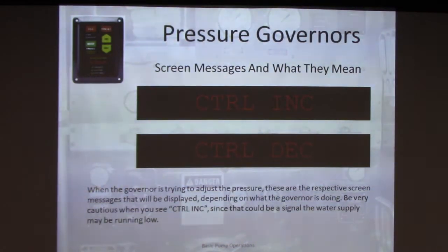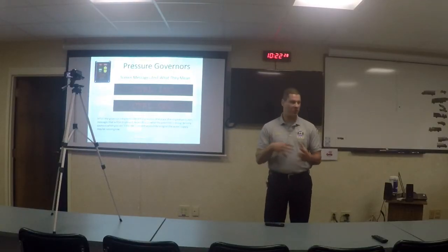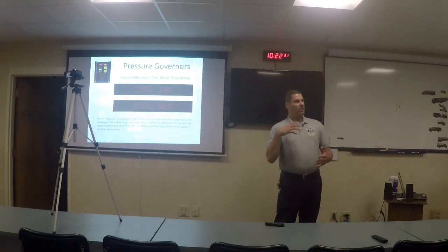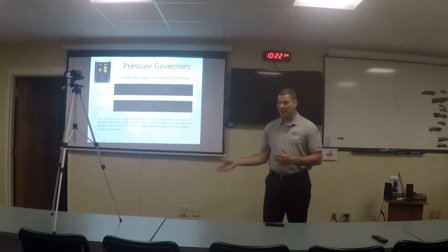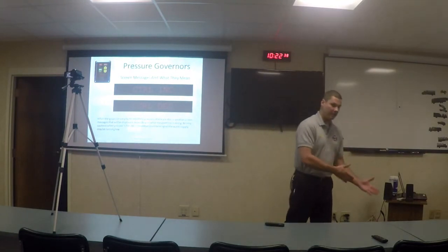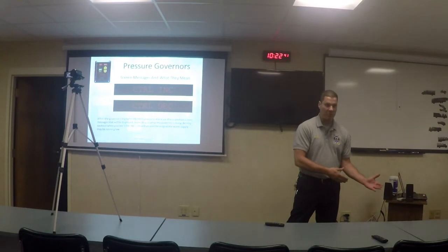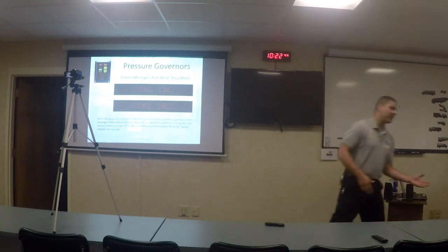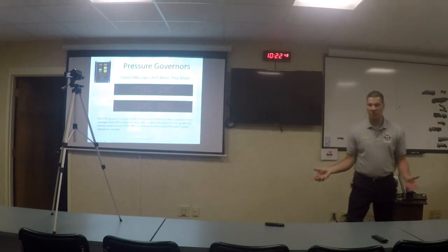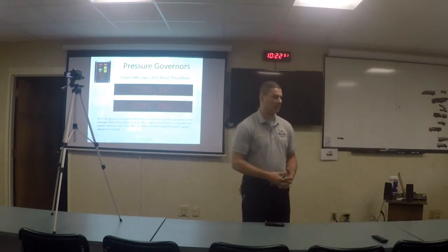Okay, what does control increase and control decrease mean? If you were to see these, that's going to coincide with the supply. Right, this is the pressure governor doing its job, okay? These terms tell you that at some point the pressure governor is working to increase or decrease the pressure. You should be aware of this because there may be an issue with the supply going on. So the moment you see these, I would take a quick look at my intake gauge just to see what's going on there. And if that seems okay, I'd also take a peek at the supply line, make sure there's no kinks in there, there's nothing going on with the hydrant, anything like that. Okay?